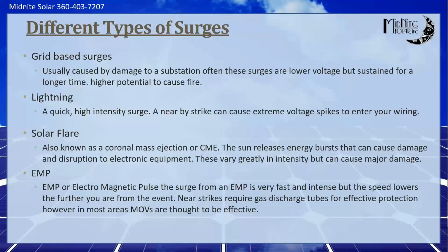Things didn't like that. If you had a good whole house surge arrestor like a Square D or a Midnite or something, they seemed to be fine. The ones that had no protection, they had 7 or 8 structure fires on that line because of that. So that's a common one, grid-based surges. Whether you're solar or not, we absolutely recommend whole house surge protection, and then also any sub panels, which we'll talk about later. Lightning is another one.